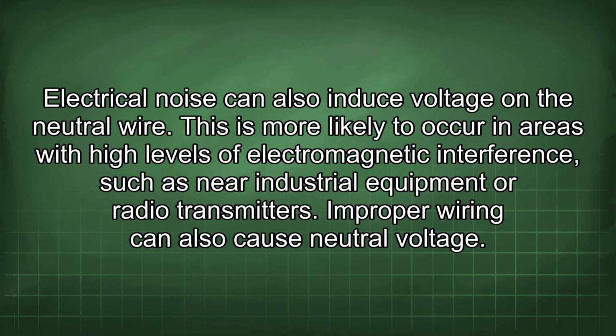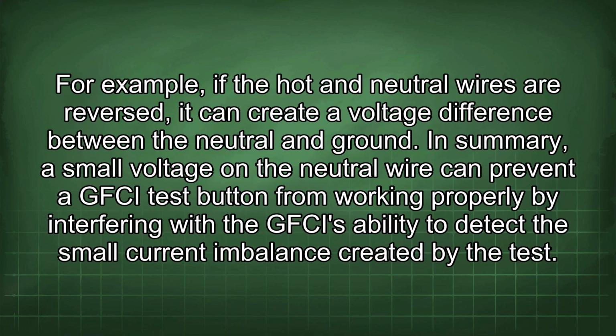This is more likely to occur in areas with high levels of electromagnetic interference, such as near industrial equipment or radio transmitters. Improper wiring can also cause neutral voltage. For example, if the hot and neutral wires are reversed, it can create a voltage difference between the neutral and ground. In summary, a small voltage on the neutral wire can prevent a GFCI test button from working properly by interfering with the GFCI's ability to detect the small current imbalance created by the test.